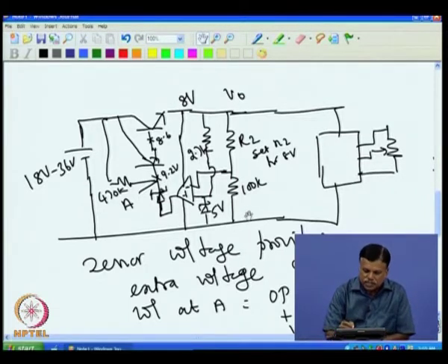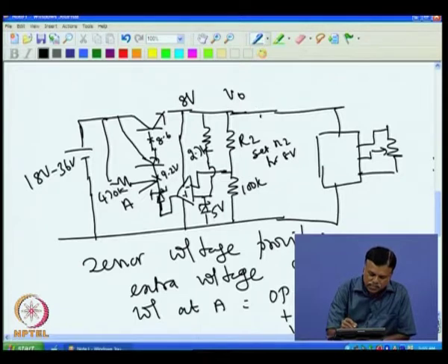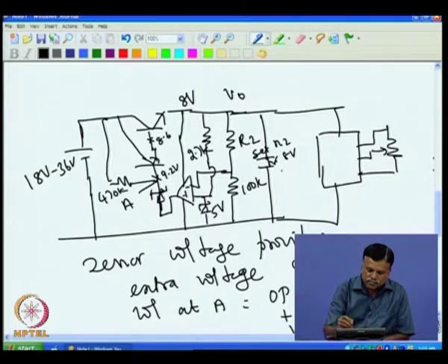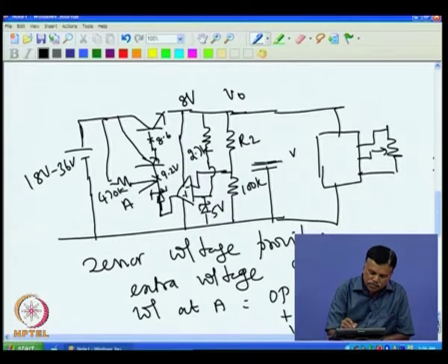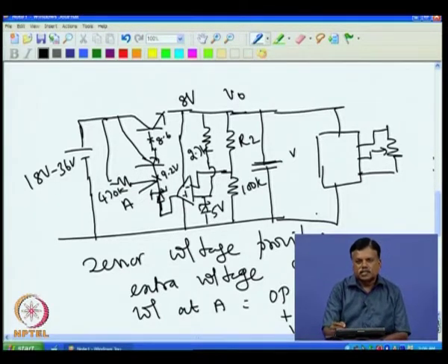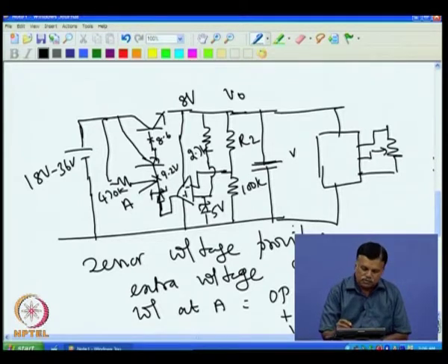And then we know that to avoid oscillation, we had to connect the capacitor here. A small capacitor can be connected across this, so that no oscillation comes in. Normally we put a capacitor here, but here we can't put an electrolytic capacitor, because this is a 4-20 milliampere system, and if the electrolytic capacitor leaks after some time, then the current drawn by this will upset the other current in the unit, and that will create a problem. So, normally we put a small value, 1 µF, 5 µF like that, not a very high value, to avoid oscillations.